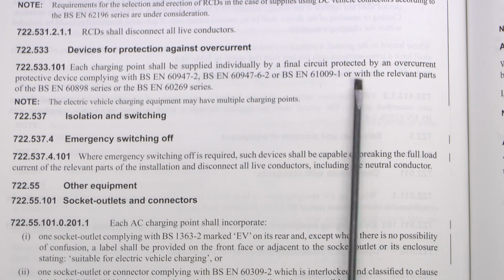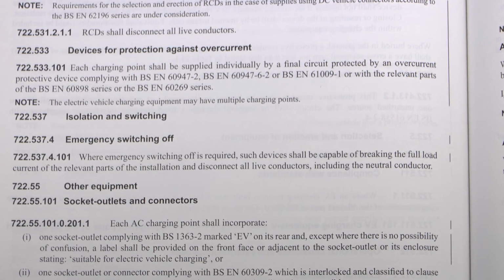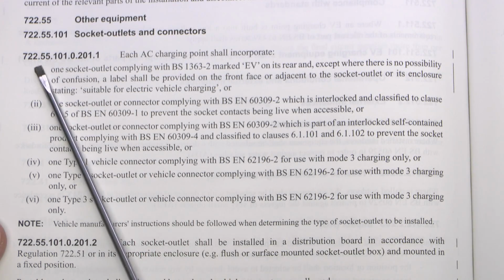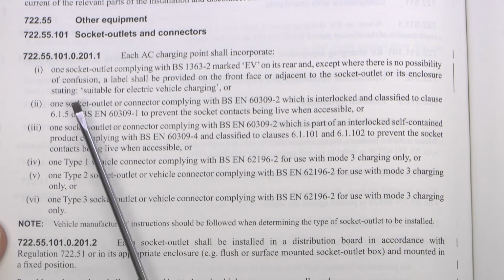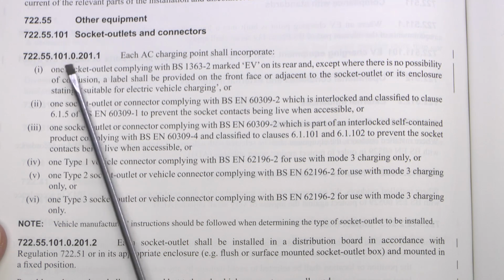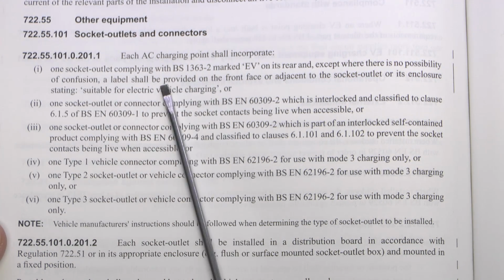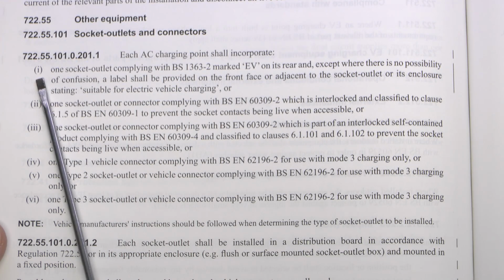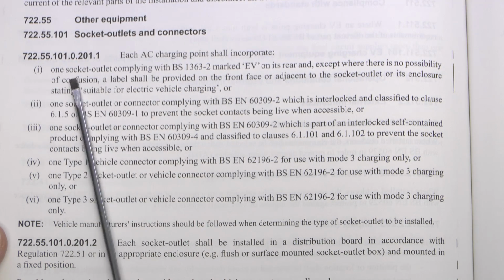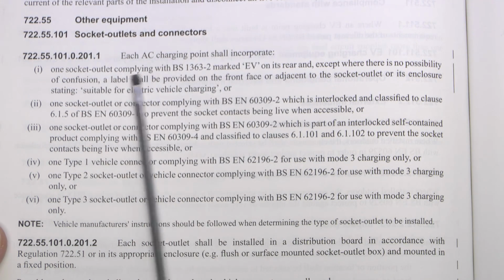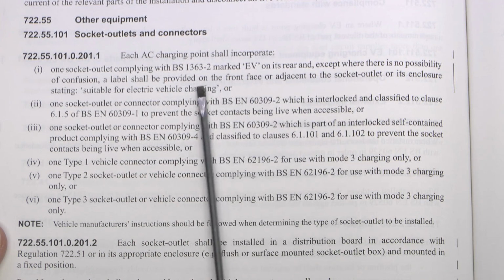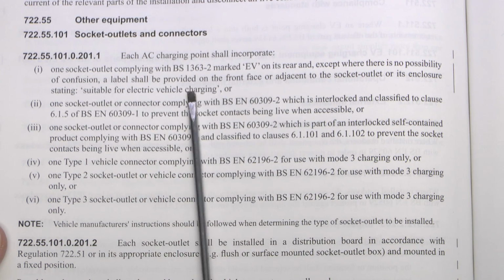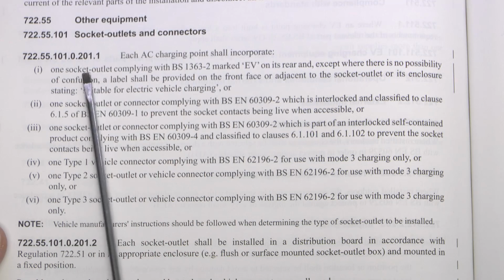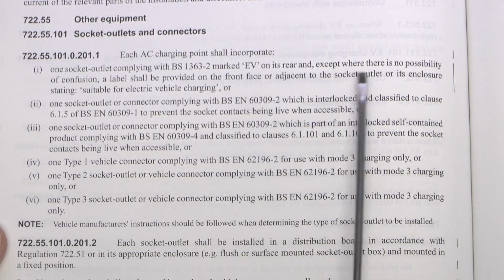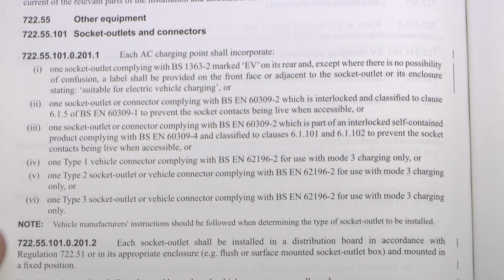But if you're going to be installing, say, 2 or 3 in one local area, they all need their own individual circuit and individual overcurrent protective device. This one here, which is one of these ridiculously extended numbers with far too many parts within, 722.55.101.0.201.1. And the difference here is that the first item, number 1, or i, has been amended. So now we must include a mark EV on the rear and also on the front face if it says suitable for electric vehicle charging. So same items there with a socket outlet, but it needs to be marked EV on the back and also marked suitable for electric vehicle charging on the front.